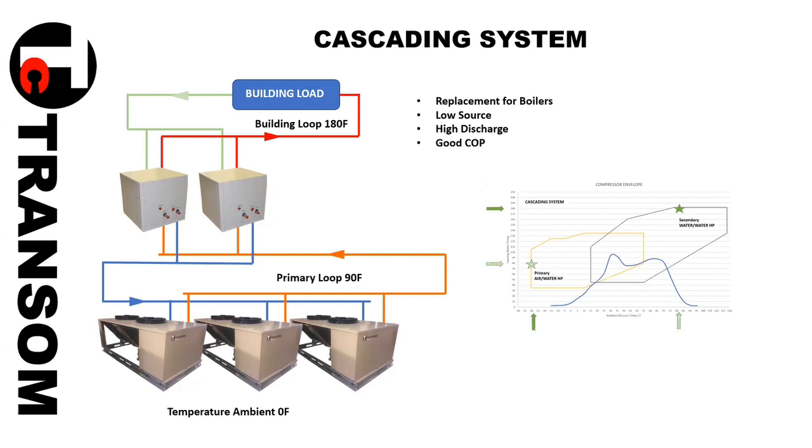Got it. And then a follow-up to that, you listed some refrigerants on one of your slides. Do you have any low GWP refrigerant systems either in development or available? There's a large push to move away from traditional refrigerants. Yes, it's becoming more and more available. But the testing and the availability of different compressors is fairly limited. Using R449A, for instance, is a good option. But say R32, you can specify it, but there are only so many compressors that Emerson and Danfoss and so on have available. And when you go to a location where it's going to be installed, not every distributor has that available. It's almost like a special order. So there are things with it.